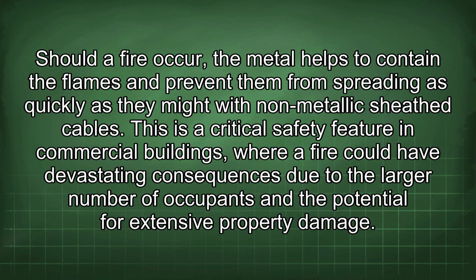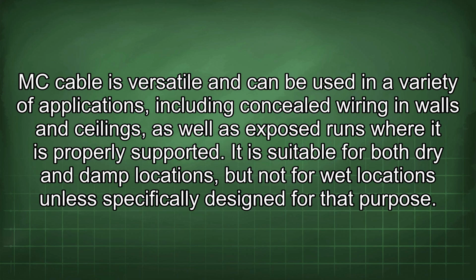Should a fire occur, the metal helps to contain the flames and prevent them from spreading as quickly as they might with non-metallic sheathed cables. This is a critical safety feature in commercial buildings, where fire could have devastating consequences due to the larger number of occupants and the potential for extensive property damage. MC cable is versatile and can be used in a variety of applications, including concealed wiring in walls and ceilings, as well as exposed runs where it is properly supported. It is suitable for both dry and damp locations, but not for wet locations unless specifically designed for that purpose.